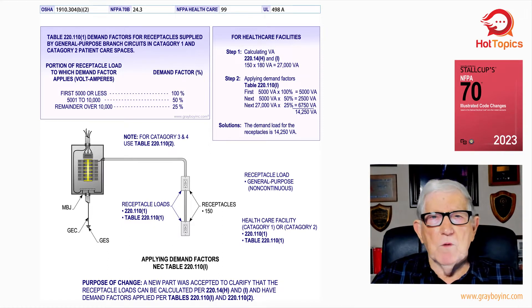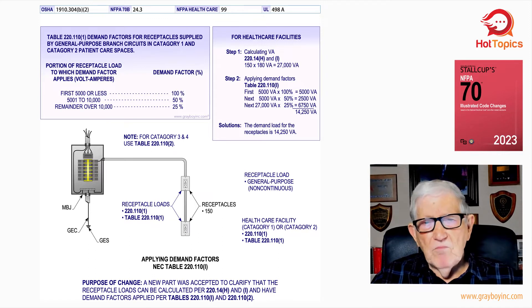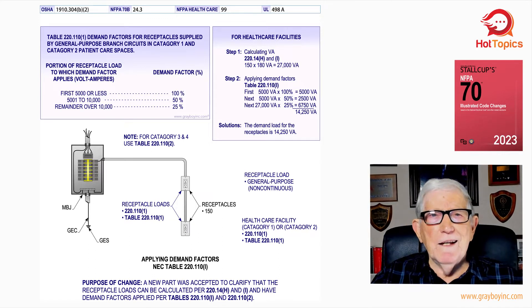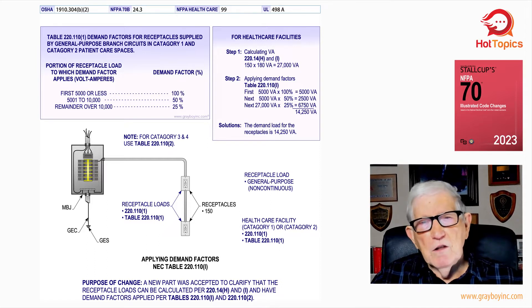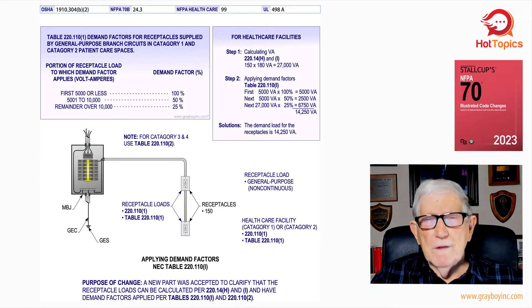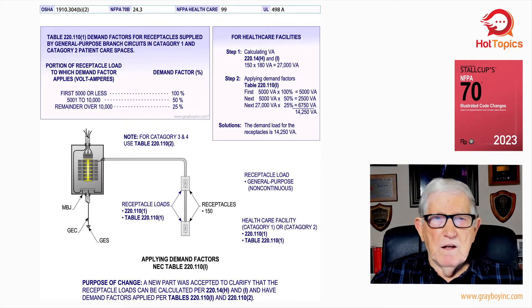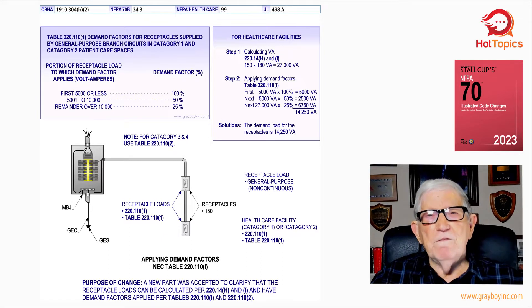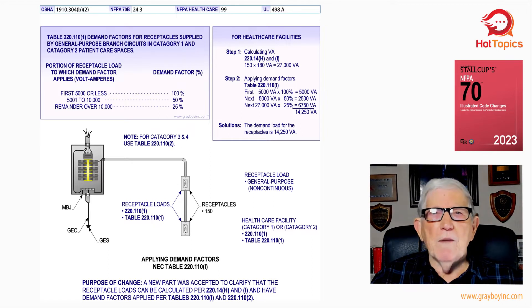Hospital is mainly what we're talking about here. Notice in this new table at the left of the illustration, table 220.110.1 for receptacle loads: if we had a certain number of receptacles, we could take the first 5,000 or less at 100% — no demand. But anything over 5,000 up to 10,000, 50% could be applied. Then anything over 10,000, 25% additional demand could be taken.